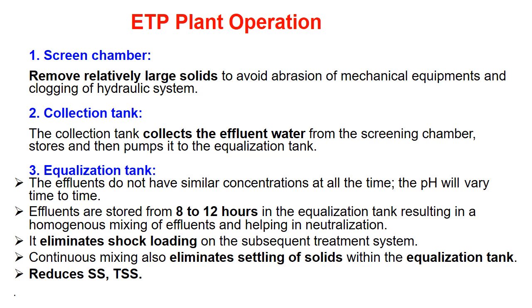Number three is the equalization tank, where all the water is mixed together. Effluents do not have similar concentrations at all times — the pH will vary from time to time or day to day. So effluents are stored for 8 to 12 hours in the equalization tank, resulting in homogeneous mixing and helping in neutralization. It eliminates shock loading on subsequent treatment systems, provides uniform quality, continuous mixing that prevents settling of solids, and reduces suspended solids and total soluble substances.